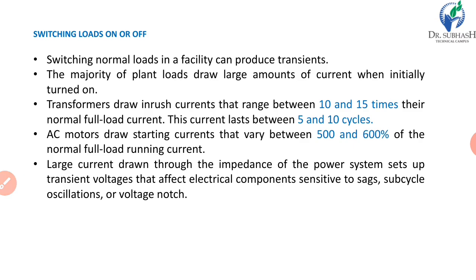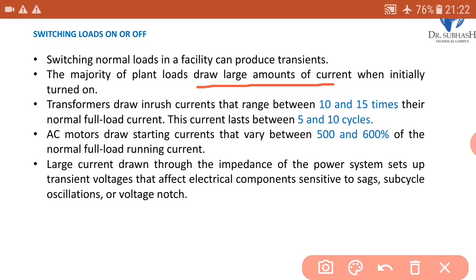Another case of transient is switching loads on or off. Switching normal loads in a facility can produce transients. The majority of plant loads draw a large amount of current when initially turned on. A transformer draws inrush currents that range between 10 to 15 times its normal full load current. So we can imagine that is a very large current. This current lasts between 5 to 10 cycles. It means this surge current may remain in the system for up to 10 cycles. So this is the characteristic of transformer inrush current.